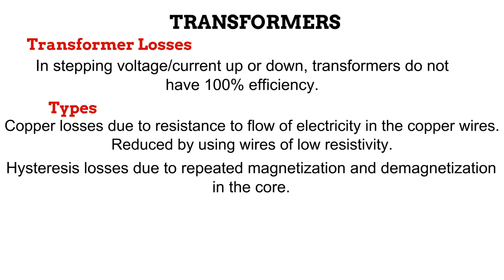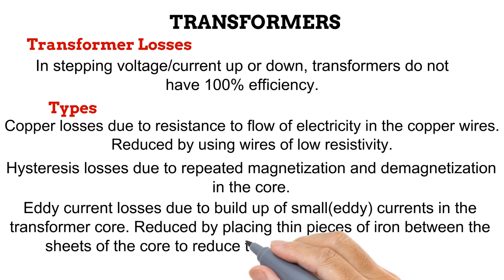Another type of transformer loss is hysteresis. As current is induced in a transformer, a repeated magnetization and demagnetization of the core is experienced. This process causes reduced efficiency. Lastly, we have eddy current losses which occur due to the buildup of small currents within the core of the transformer. If thin pieces of iron are placed between the sheets of the transformer core, these eddy currents are unable to be transmitted and losses due to them are thus reduced. This method of reducing eddy current losses is called lamination.